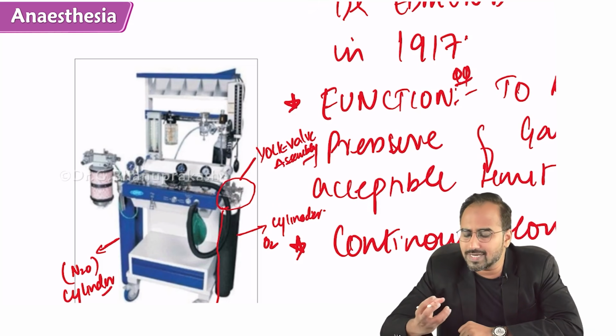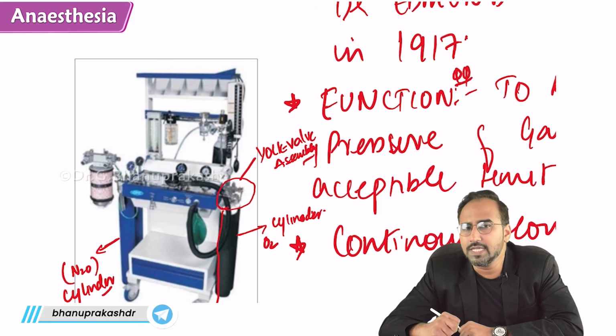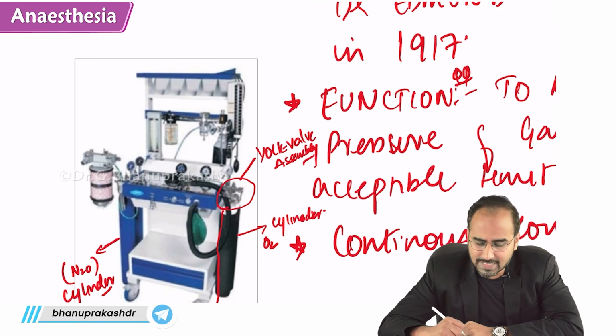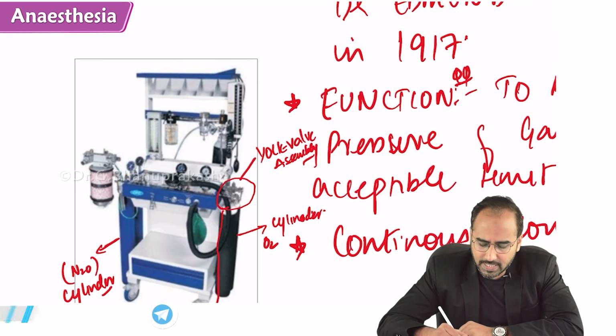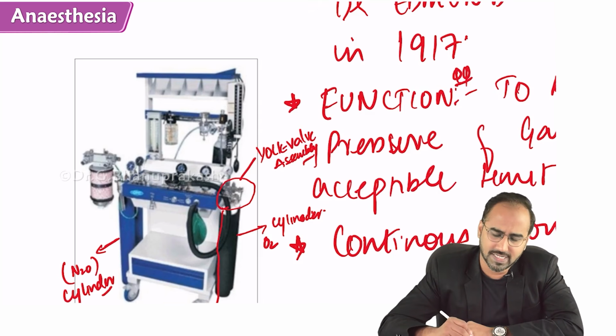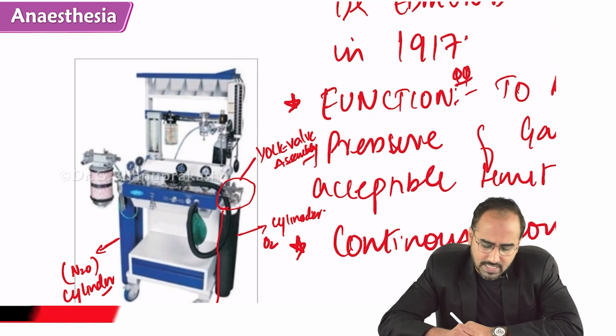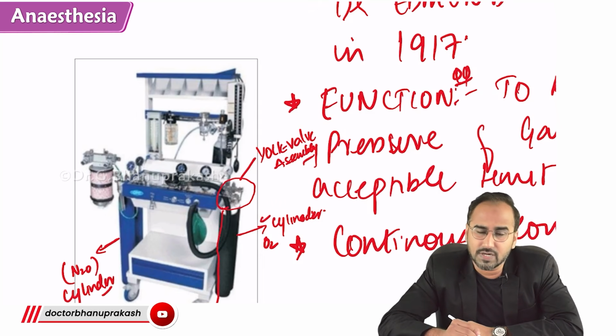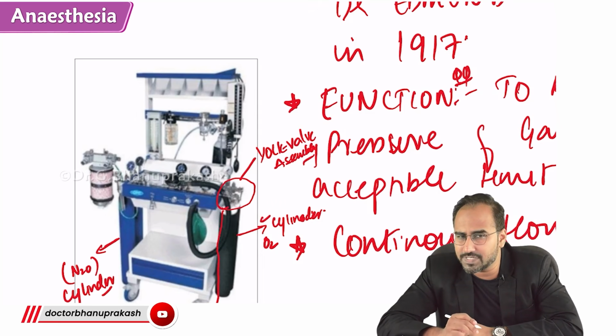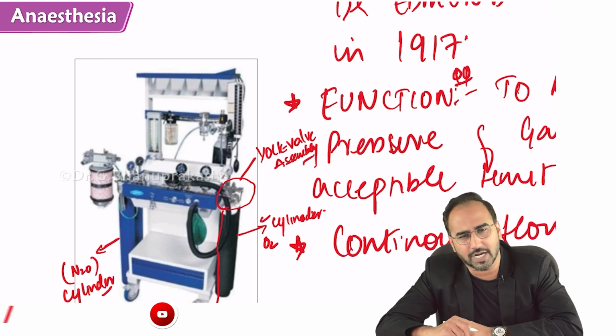So if you look at the inner surface of the yoke valve assembly, you will find a system that prevents wrong attachment of the cylinder. What is that system called? The pin index system. So once again, the parts we have discussed: first is the cylinder. How is the cylinder attached to the machine? With the help of a steel assembly called the yoke valve assembly. And on the inner surface of the yoke valve assembly, you find a system that prevents wrong attachment.